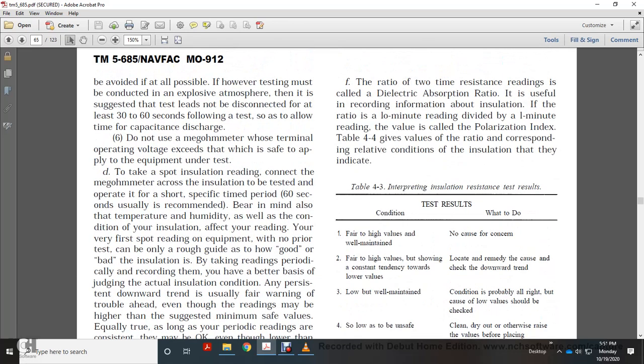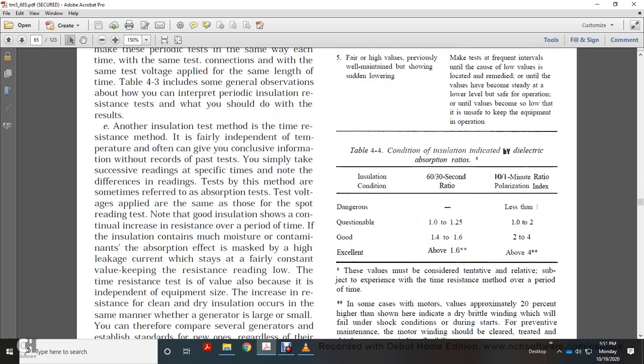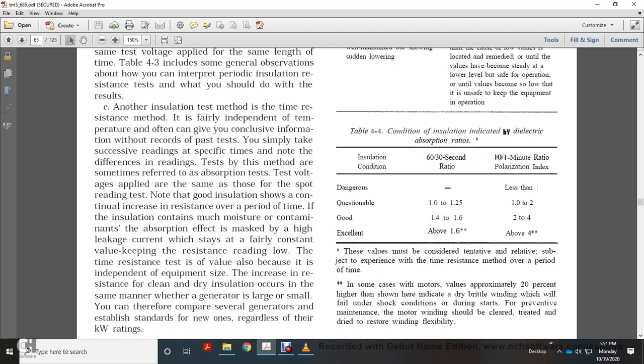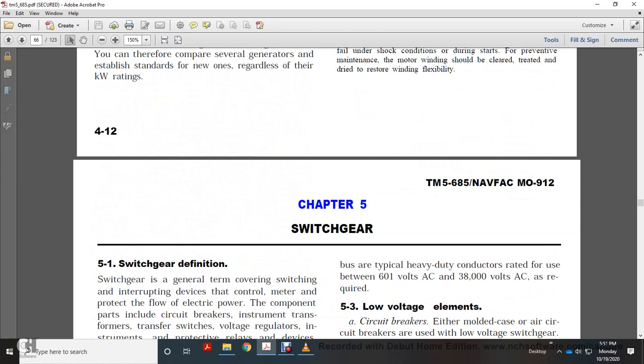The ratio of the two resistance readings is the dielectric absorption ratio. The ratio of the 10-minute reading divided by the 1-minute reading is called the polarization index. Table 4.4 gives the value of the ratio and the corresponding relative condition of the insulation. Table 4.3, interpreting insulation resistance test results, and Table 4.4, condition of the insulation by dielectric absorption ratio. Chapter 5, Switchgear Testing.